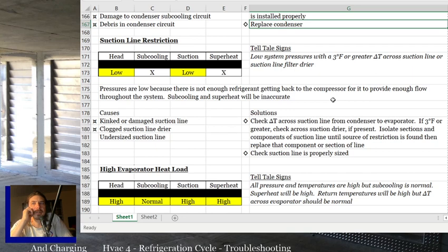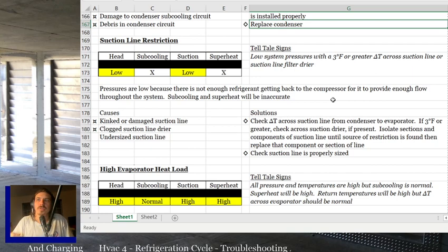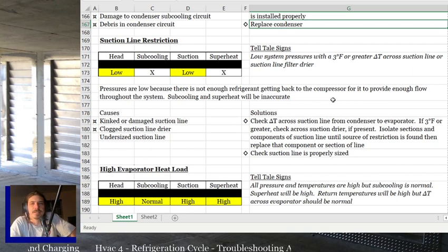So basically, the only real way to tell is a 3-degree or greater temperature difference across the suction line or the suction line filter dryer.